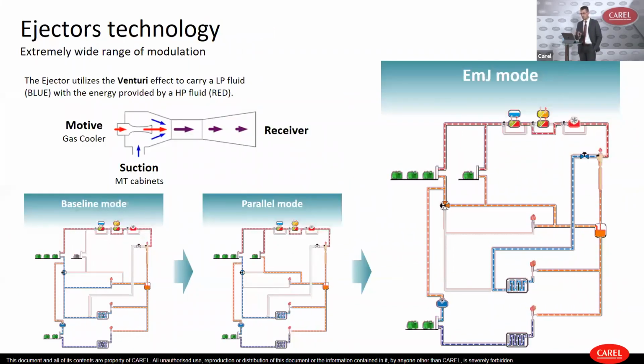So in this slide, it is explained very quickly the ejector concept that uses the Venturi effect in order to bring a low pressure fluid that is coming from the medium temperature cabinets in this case, and it is pumped into the receiver by using a motive, high pressure, and even high temperature fluid that is coming from the gas cooler. So in the first section of the ejector, the two fluids are mixed, and they are reducing the pressure and increasing the speed in the convergent.